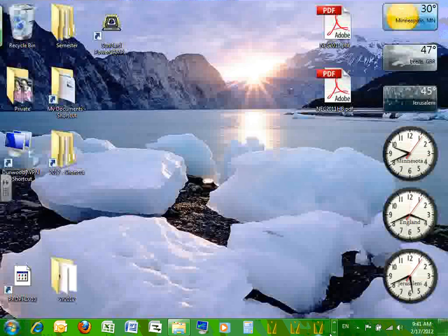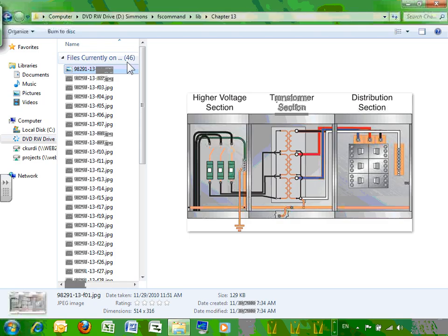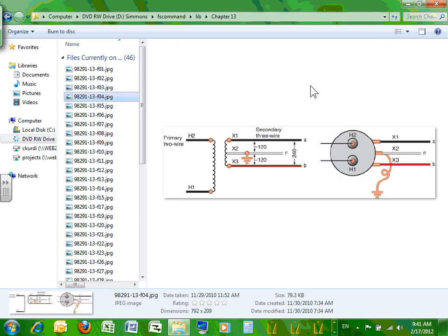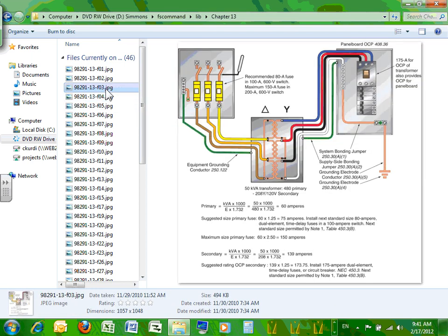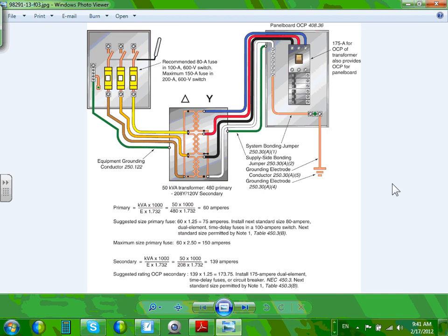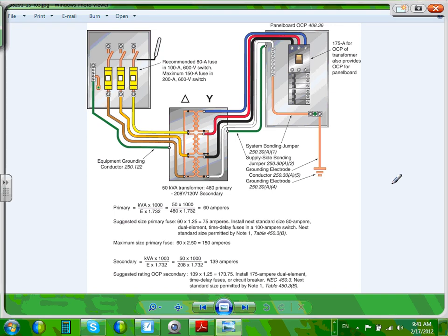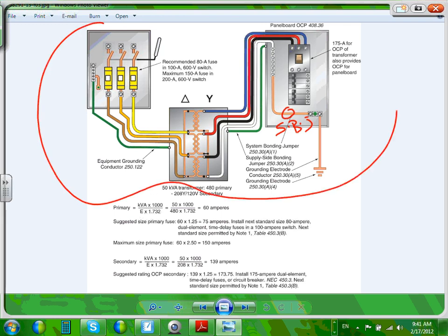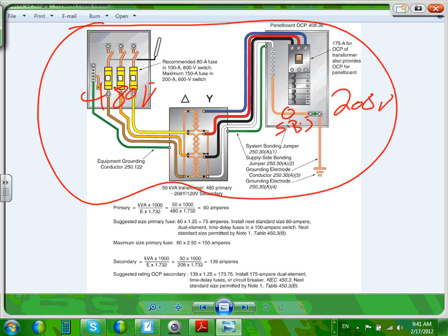Let me see if I can find it. Of course, you can never find it when you want something. Okay, there was one. Okay, here you go, right here. This one is called the system bonding jumper. Why system? Because I own and operate all of the following. This is all in-house. Make sense? We have the transformer. We took the 480 volt inside our building and converted to a 208 system, and we created a new neutral. They call it the system bonding jumper. Almost always, when you take a 480 to a 208, you have a system bonding jumper.